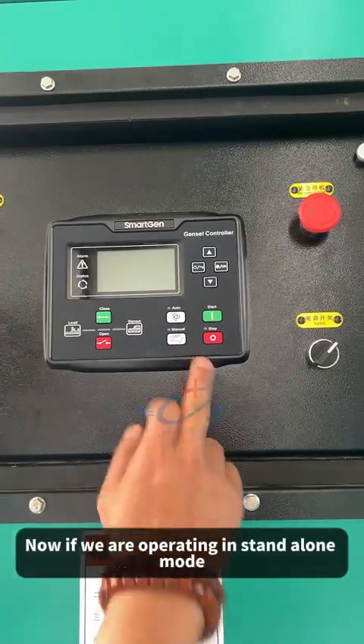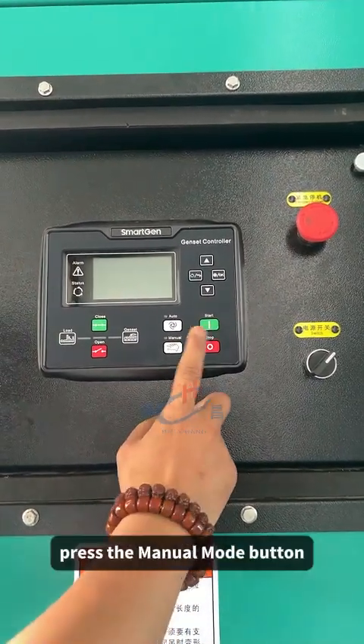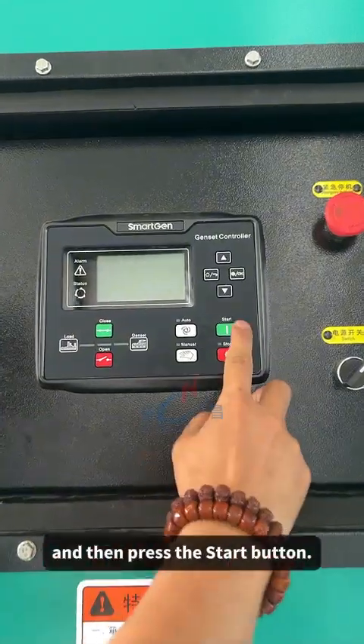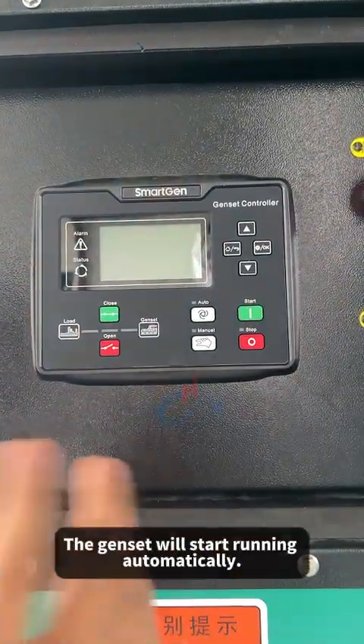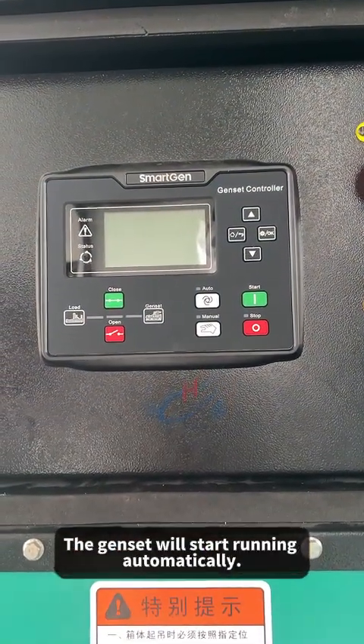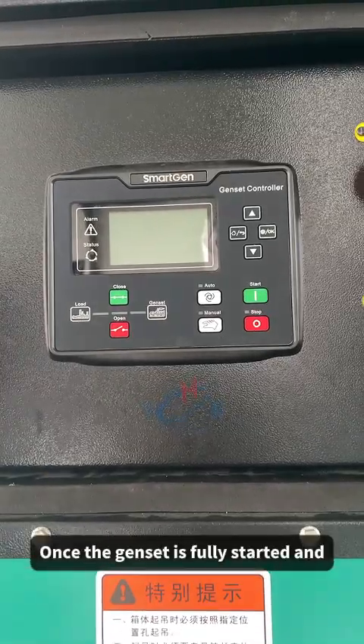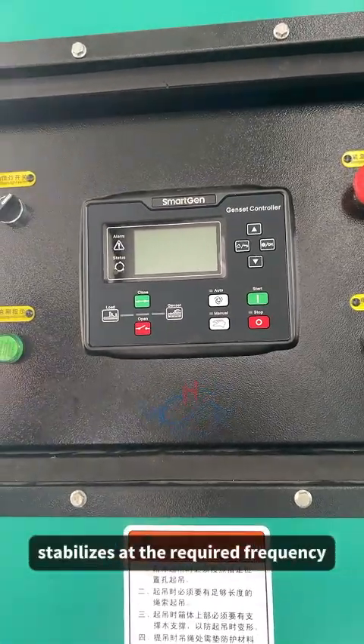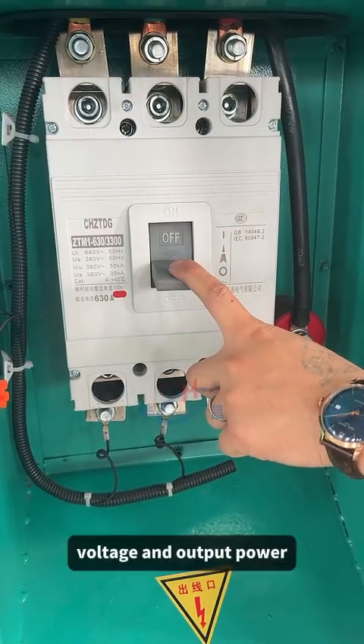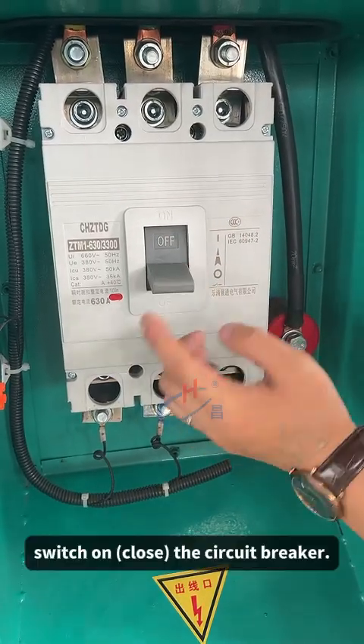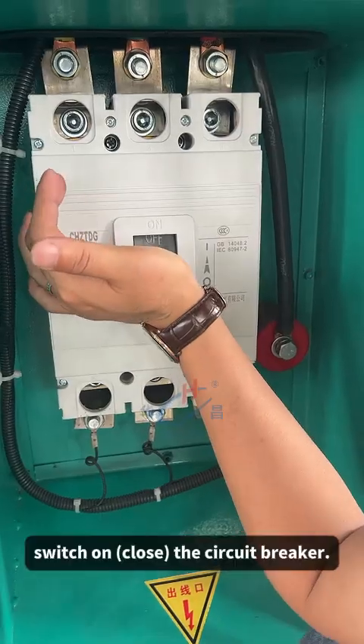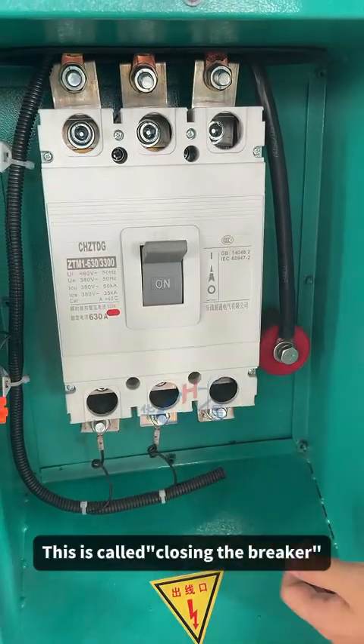Now, if we are operating in standalone mode, press the manual mode button and then press the start button. The genset will start running automatically. Once the genset is fully started and stabilizes at the required frequency, voltage, and output power, switch on (close) the circuit breaker. This is called closing the breaker.